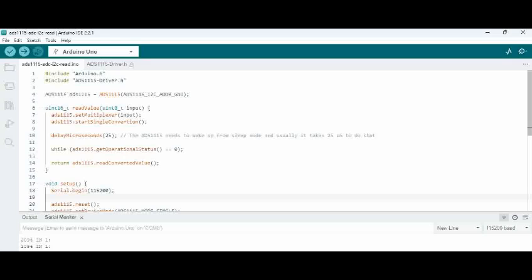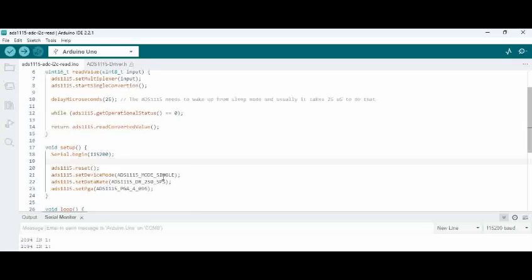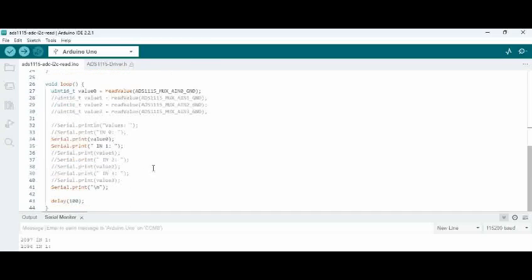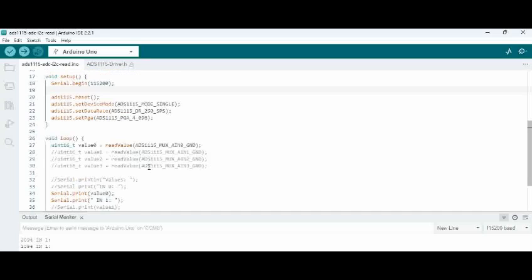Now, one more point to remember here is we are actually displaying the value that is being read in the register here. If you want to specifically convert it into a proper analog value that you are reading, you have to create a table on your own matching the physical value with the value that is being read, and use appropriate conversion to get the output. So that is how you have to modify this application code to get the accurate value.